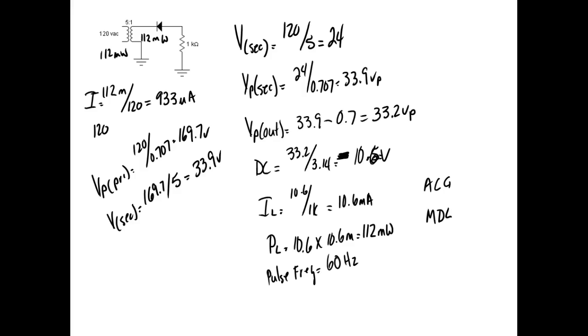Which one's fast blow? ACG. We don't use these, very seldom use these in power supplies. An MDL is a time delay fuse, so what it does, most people call them slow blow fuses. So they'll handle an overcurrent over time, but it won't be long enough to burn up stuff, and the problem with power supplies is we're charging stuff up, or we're putting that shock on there.